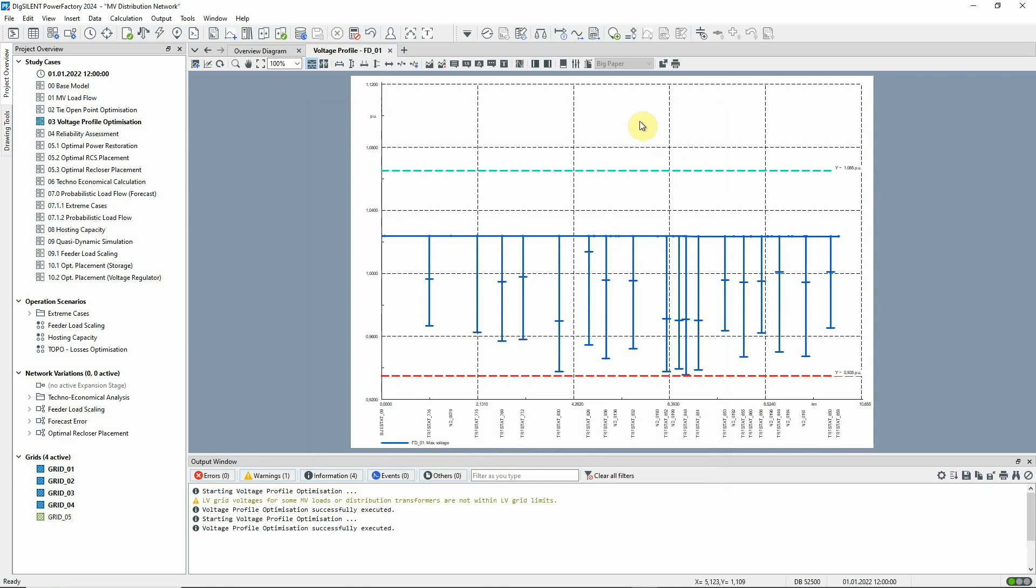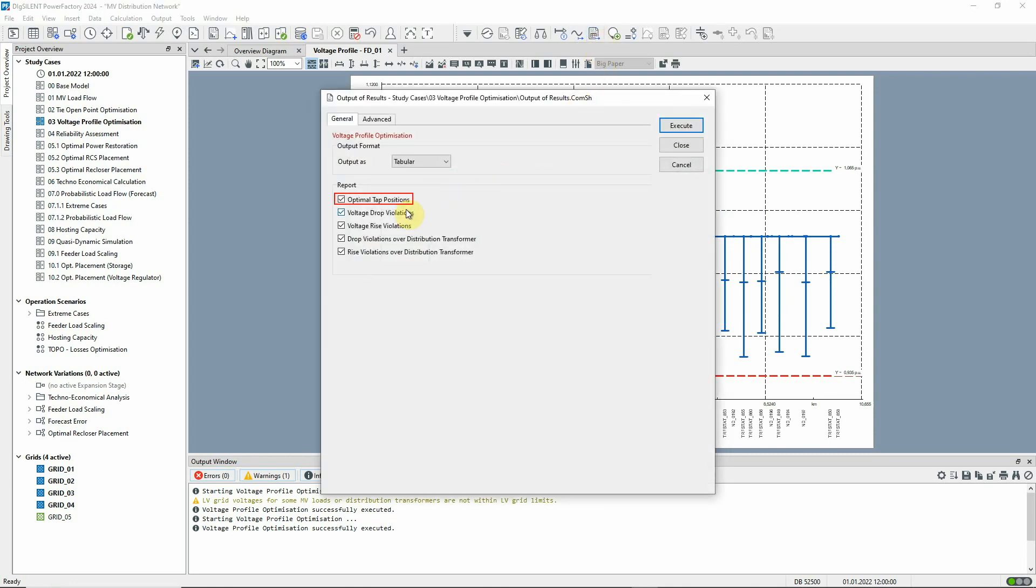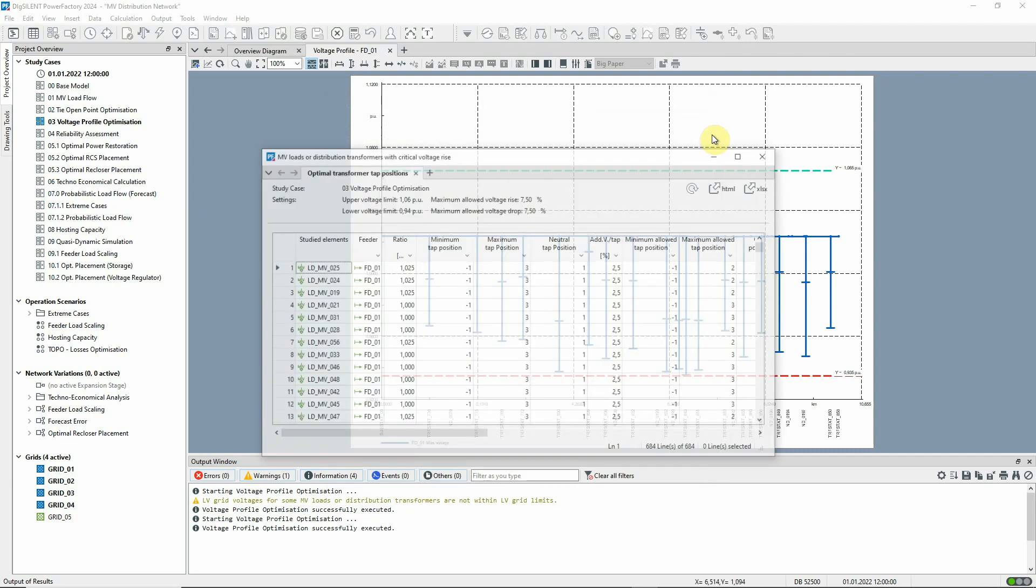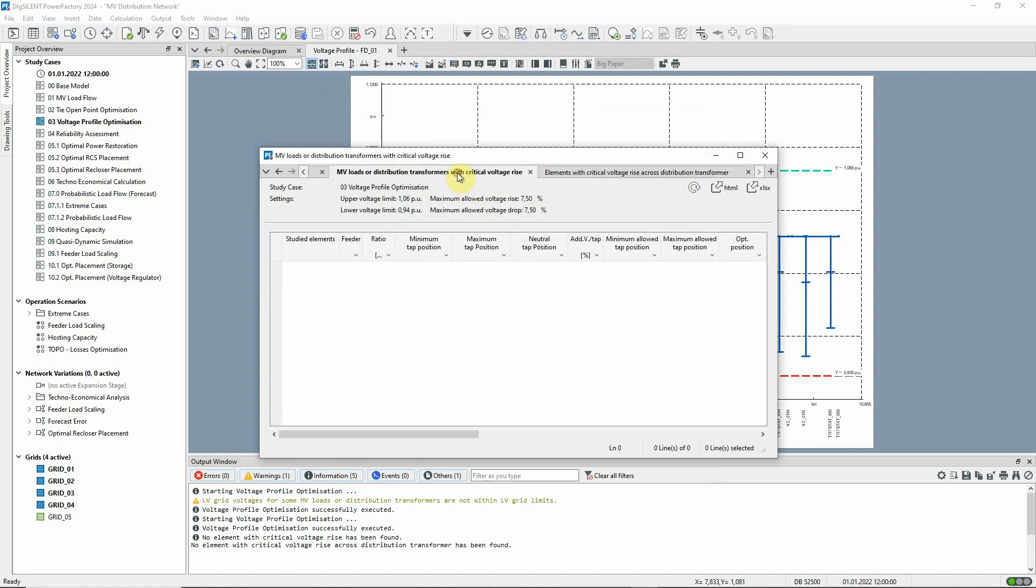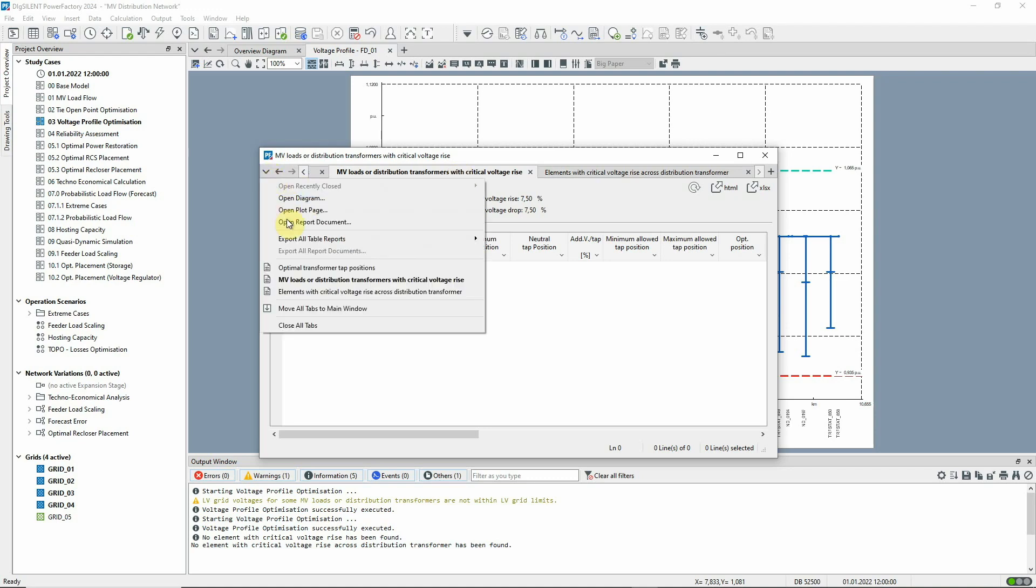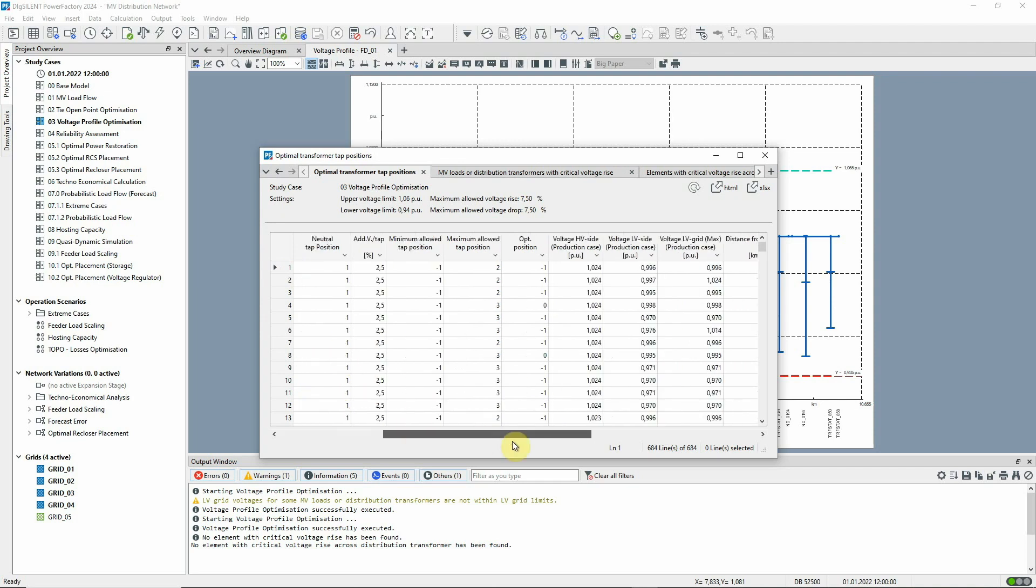Let's run the reports again. An extra report is now available, which shows the optimal tap positions that have been determined. We can see that no critical voltage rise across the transformer is reported. And all elements are within the upper voltage limit. This report shows the optimal tap positions determined by the analysis.